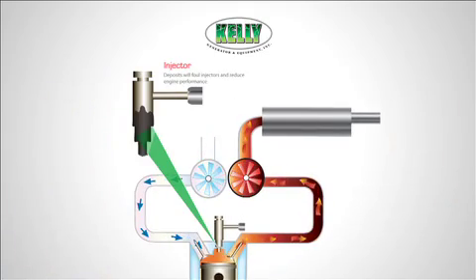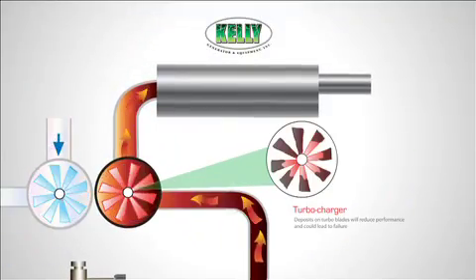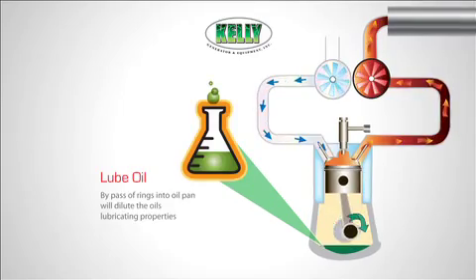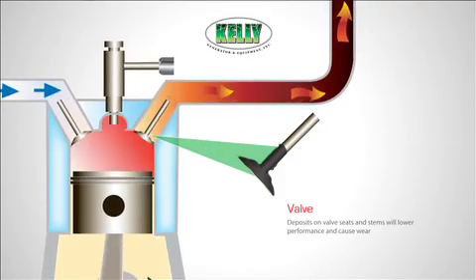A generator that is continually run on a light load will start to exhibit the symptoms of wet stacking. Carbon deposits will form on injectors, pistons, rings, turbochargers, valves, and accumulate in the lubrication oil. All of these conditions will result in reduced performance and reduced engine life. Maintenance downtimes are also extended because of the additional work required to remove carbon deposits from key internal components.